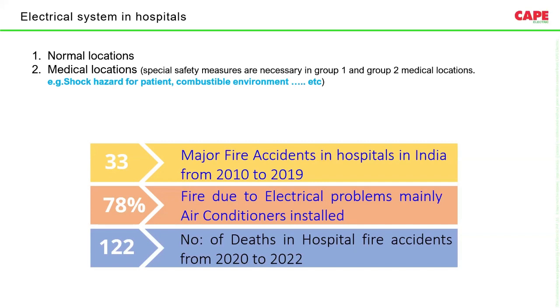First, we should understand that electrical installation in a hospital is a special thing. There are normal locations and medical locations. A medical location means a location in a hospital which is classified as Group 0, Group 1 and Group 2, especially Group 1 and Group 2 medical locations, where biomedical equipment are constantly in touch with the patient and most often the biomedical equipment are bypassing the skin.